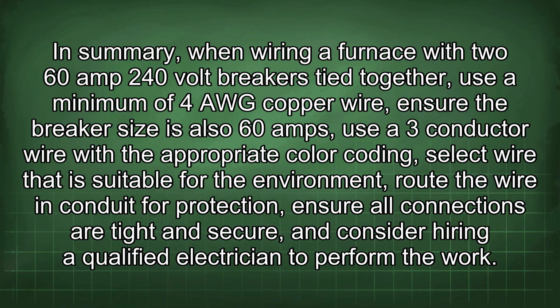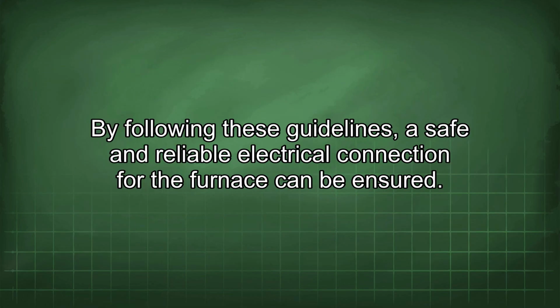In summary, when wiring a furnace with two 60-amp 240-volt breakers tied together, use a minimum of 4 AWG copper wire. Ensure the breaker size is also 60 amps. Use a 3-conductor wire with the appropriate color coding. Select wire that is suitable for the environment. Route the wire in conduit for protection. Ensure all connections are tight and secure, and consider hiring a qualified electrician to perform the work. By following these guidelines, a safe and reliable electrical connection for the furnace can be ensured.